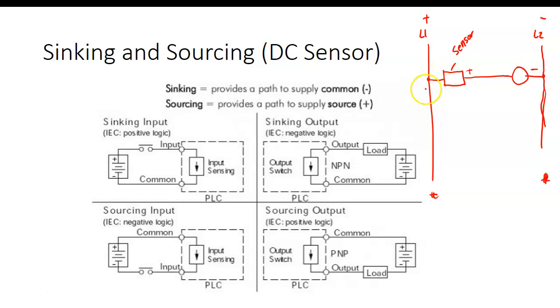Any sensor that supplies a plus on DC is referred to as a sourcing sensor, and your load would use minus, so your load would be sinking. On DC, the minus is sinking, the plus is sourcing. That's just the naming convention.